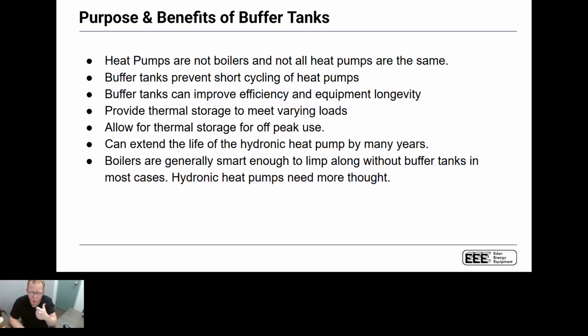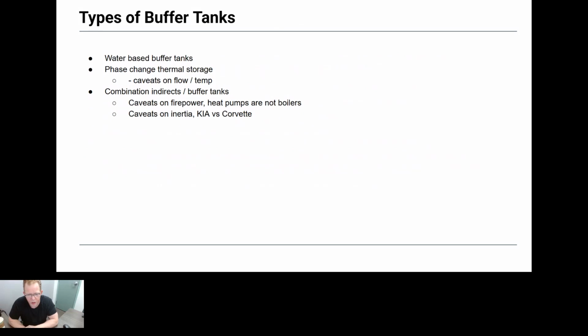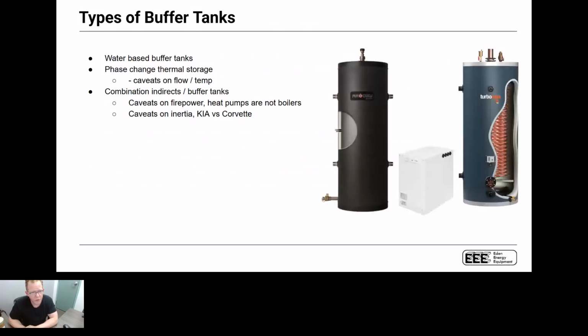And the key thing is, when we utilize the buffer tank and we don't allow the system to constantly cycle on and off, it's going to extend the life of the hydronic heat pump by many, many years. We do not want to have it banging on and off. It can be very problematic for the unit.